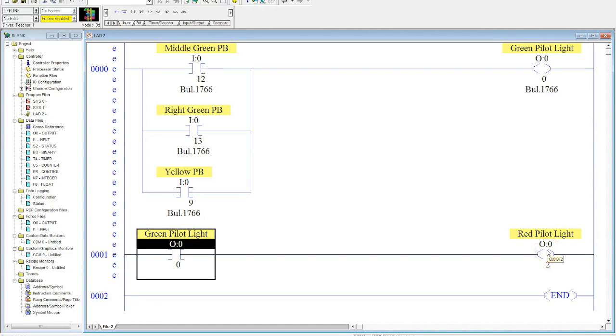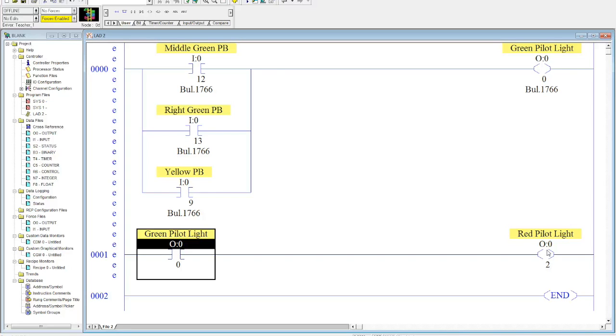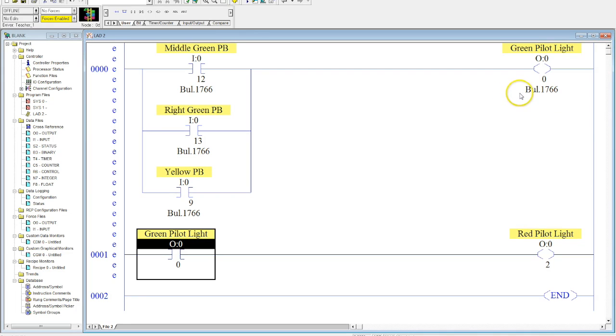Now, this is the exact same program. It's going to act exactly like the previous program. But, the subtle difference here is that if later on I want to change the logic here where my pilot light maybe comes on in a different circumstance, this is super important to be able to do because you don't want to start messing with a lot of inputs and outputs that are controlled by different inputs in the same rung. It just becomes a mess to troubleshoot and a mess to program. So, I'm going to download this.